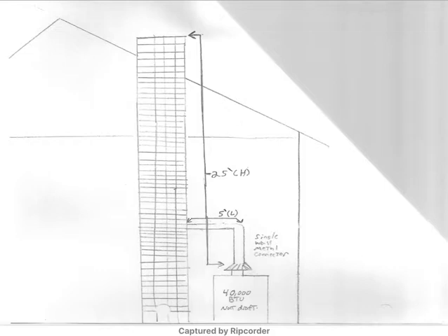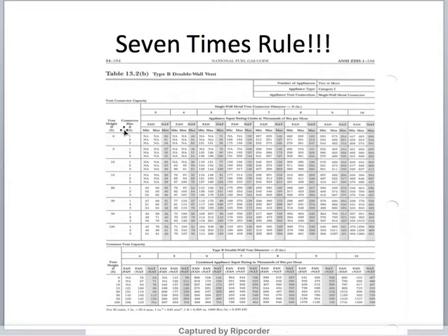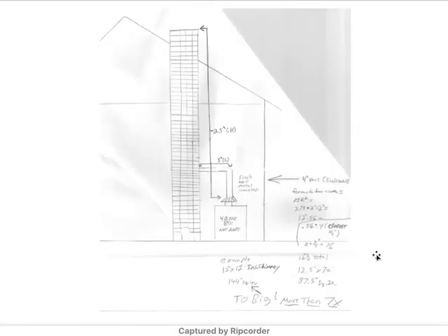One thing I want to show you is the 7x rule. Real quick, we'll cover this a little bit more in a math class that we'll do on here, but I wrote it down. I got all my chicken scratch here. So what you want to make sure is that the inside of this chimney here, this masonry chimney, is not 7x larger than the area of this flue pipe. So we use the formula for area of a circle, because this is going to be round, correct?